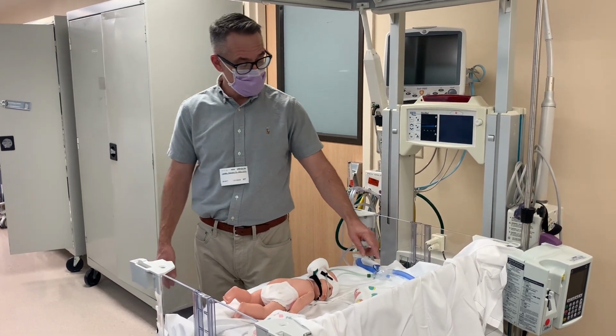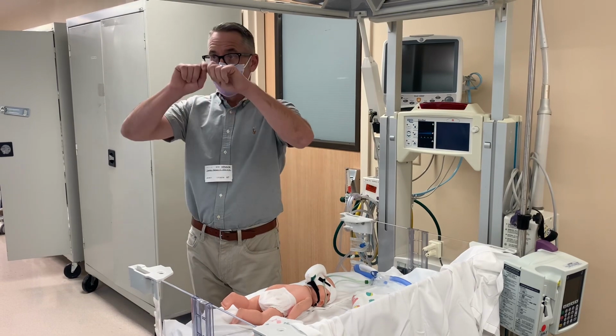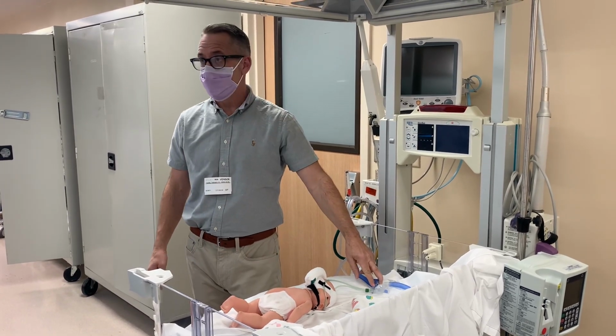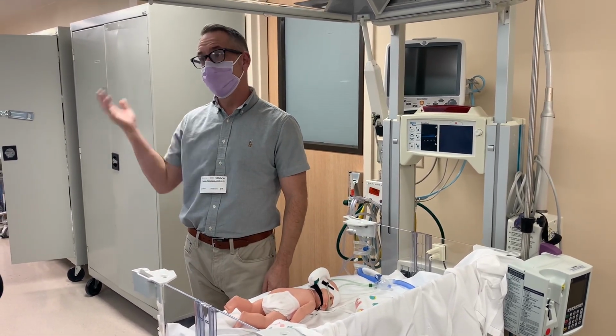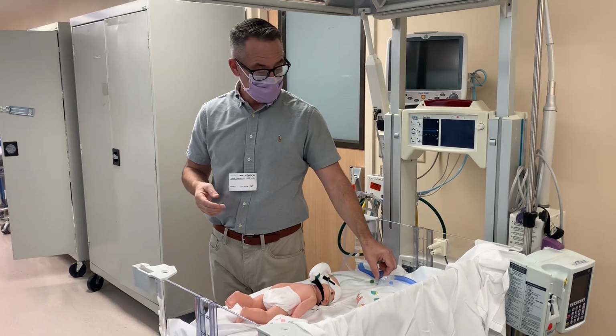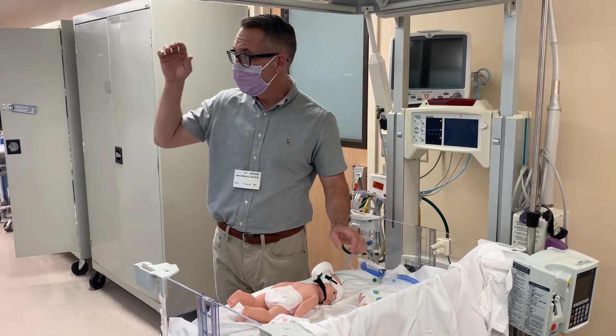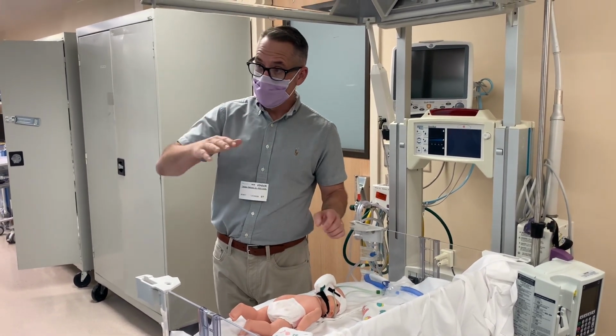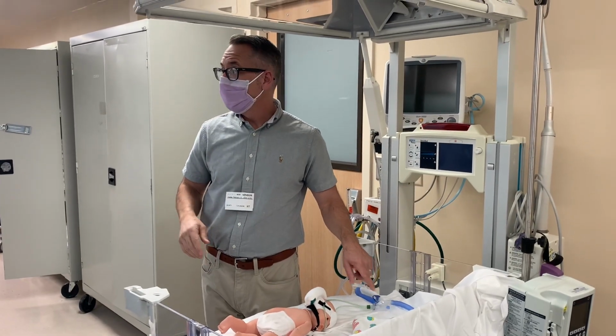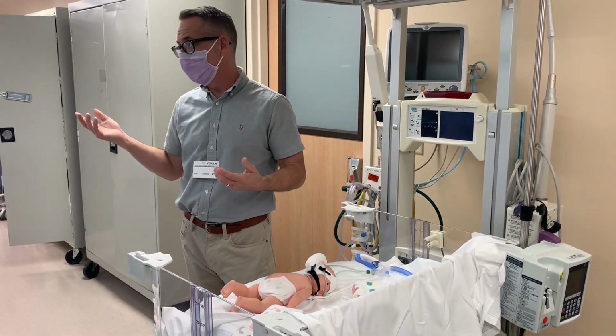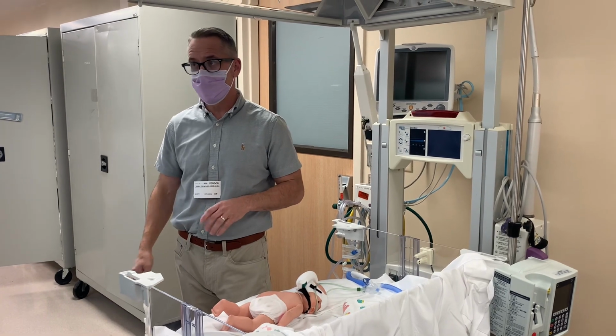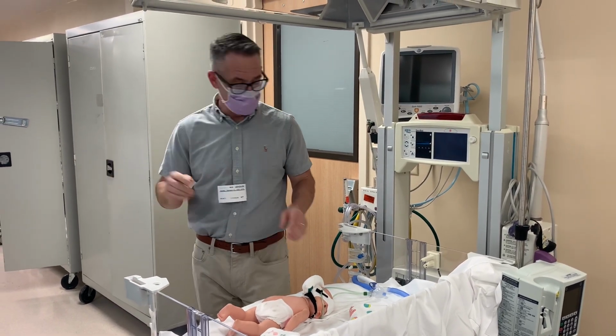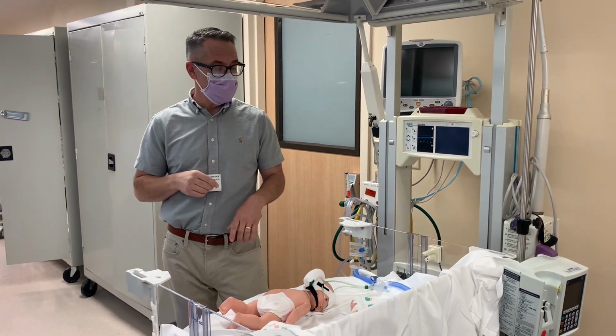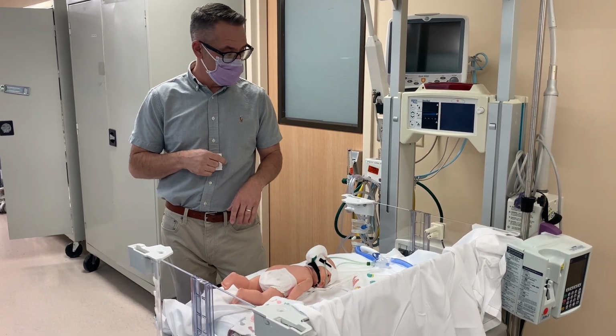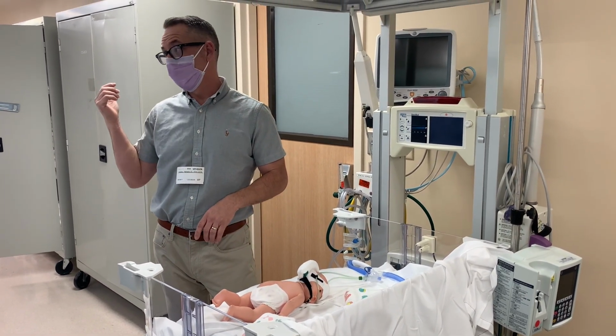The other question I had is, can we use those kind of strips that go on the outside of the temperature probe as a reflective? That's for infant warmers. They used to create a reflective strip that would go over the temperature probe because the infant warmer would shine radiant heat onto this, and that would cause the temperature to spike, but that's for infant warmers only. Okay.